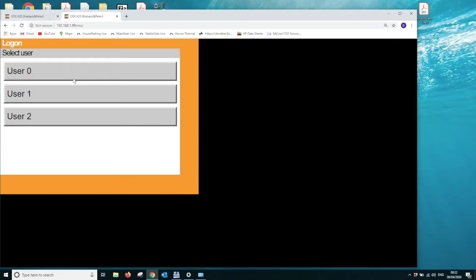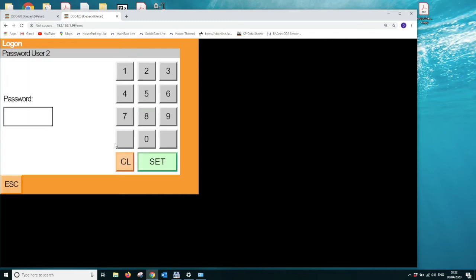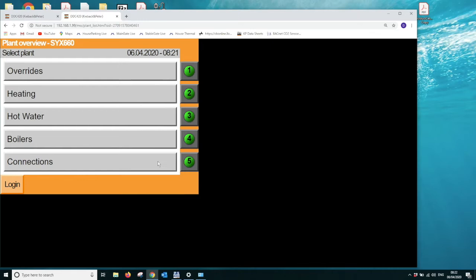Okay, so we now have access to the controller, and we can log in using user level 2. We need user level 2 to gain access to the configuration parameters which allow us to configure the application of the controller. So I'm going to choose user 2, and the passcode is 0112, and then click set. Okay, so now we've got access to the controller. So you can see that there are 5 menus on the screen.